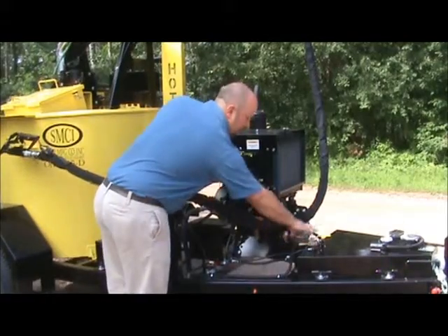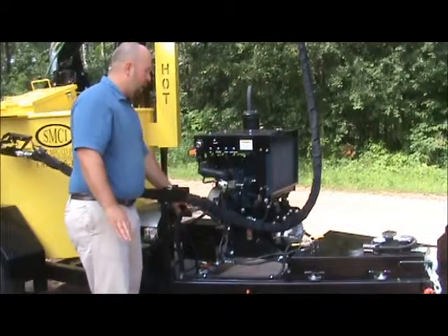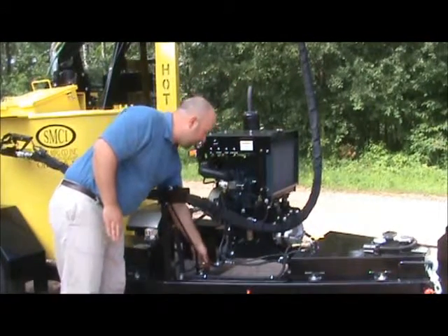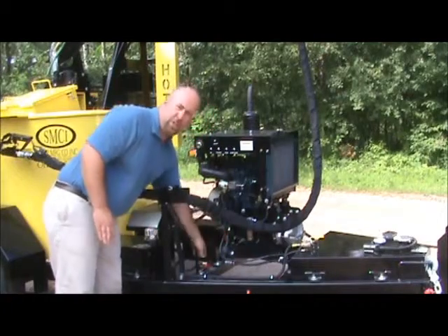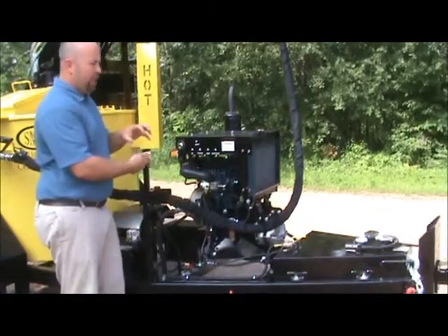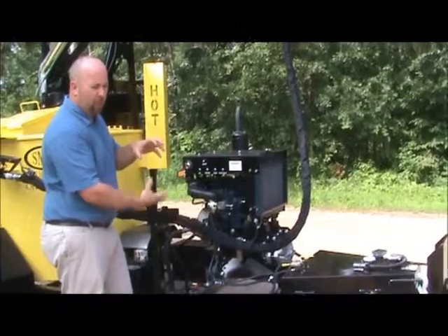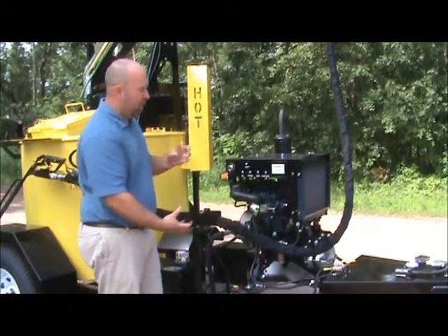The tank also has a service valve for the burner filter, so you can change that burner filter. The burner filter is located just down here, and to change that, there's just a bolt on the bottom. You take the bolt out, and the filter actually comes out of the inside of it.